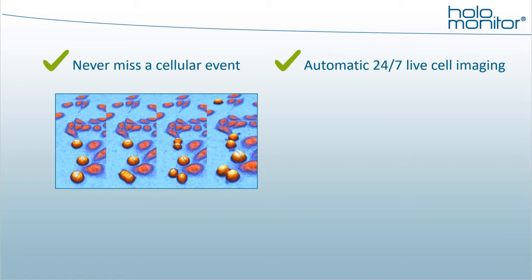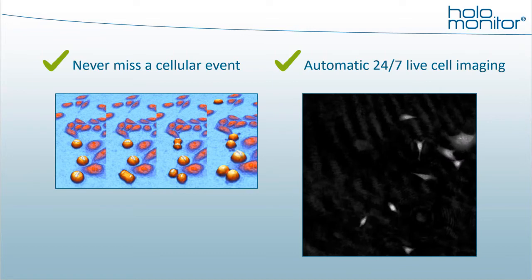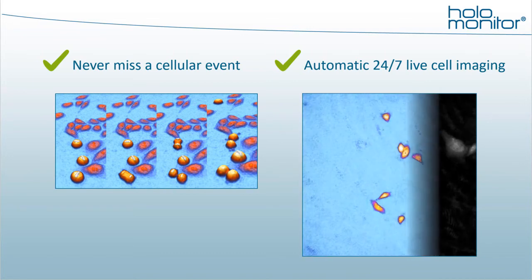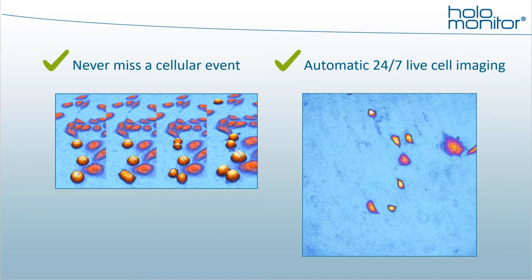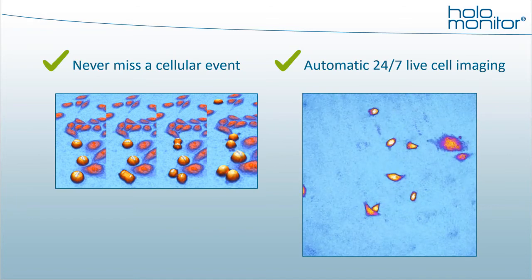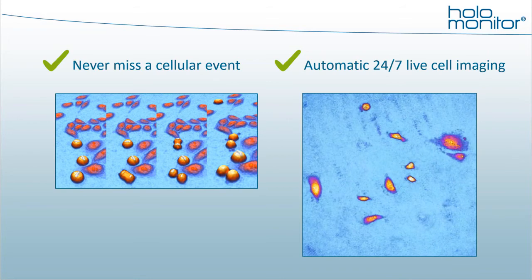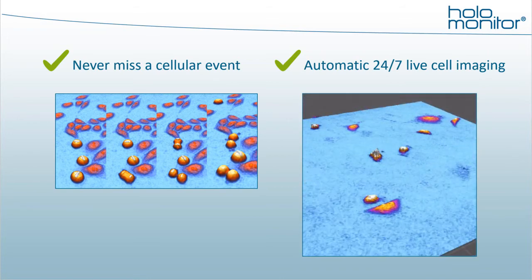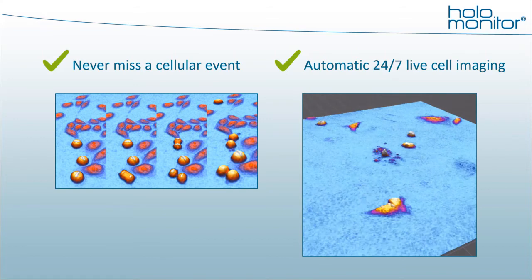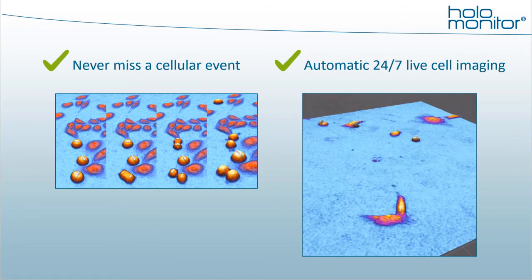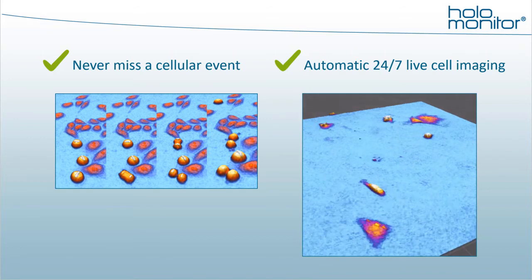Unlike traditional methods, you don't need to handle the cell sample at each imaging time point. This imaging system is working for you automatically. Your live cell TV doesn't have to be just black and white. Holomonitor uses digital holographic microscopy to reconstruct 3D images of the cells in the software. No cellular labels are necessary for this technology, making it non-invasive and cell friendly.